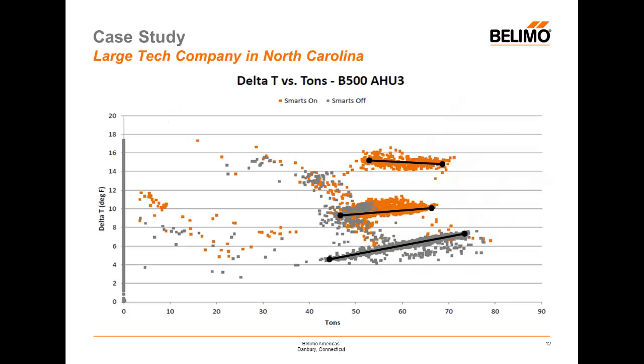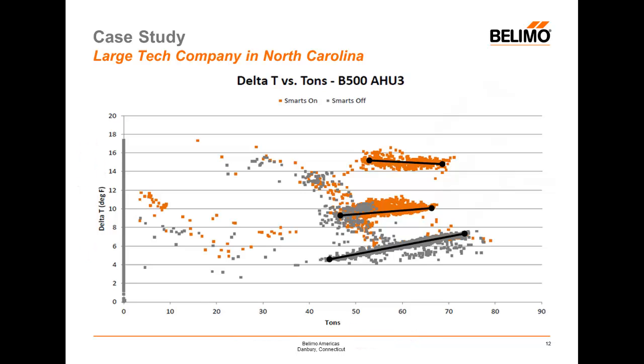Let's take a look at one last case study. It comes from a large technical company in North Carolina. We have been asked not to use their name for marketing purposes, but they have been willing to share their data. What you're looking at here is a graph where we are plotting tons of cooling across the x-axis and the corresponding Delta-T on the y-axis. The three separate clouds of information represent three different control modes. With the energy valve in place on a single air handler, it was run first in position control mode — basically a standard control valve where each value of the control signal controls how open or closed the valve is, similar to any characterized ball valve or globe valve.